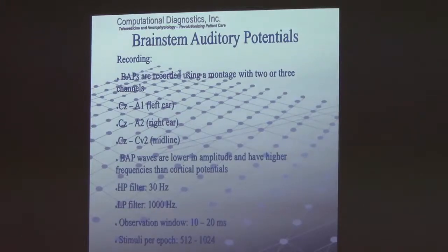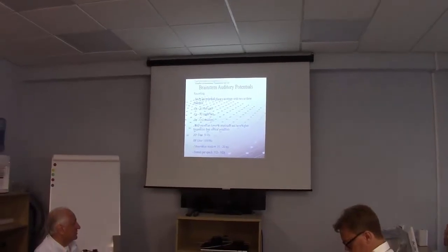The number of stimuli that we'll average is typically 512. Very seldom do we have to go more than 1,024. Many times we can get responses with 256 stimuli. If you can get it with 256 stimuli at 17 hertz, it's only 15 seconds to get a response. So it's very close to real time.